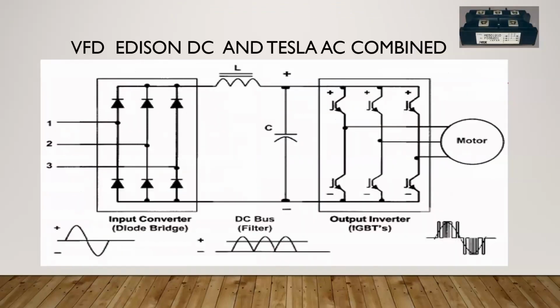And you see a lot of that happening more and more today. We actually have units that are single phase rated input, give you three-phase out, and they'll mount directly onto the motor, up to about 15 horsepower now, and they're watertight. You can stick them right on the motor. They have heat dissipation, they're made with an aluminum housing, so they self-cool. We use those a lot.